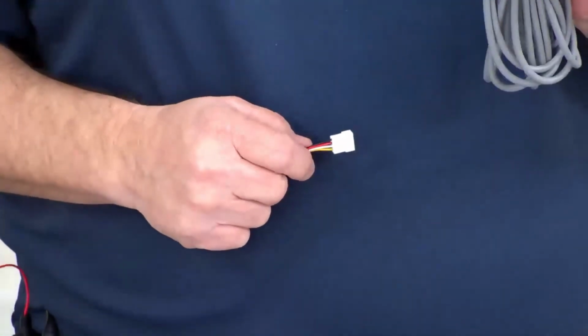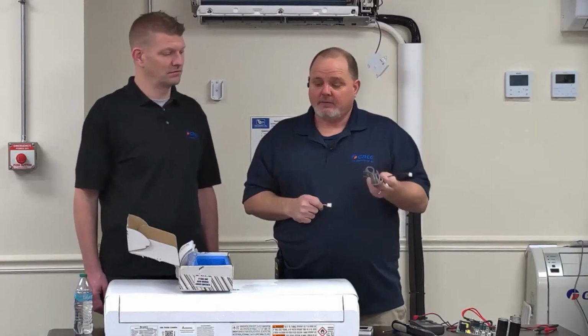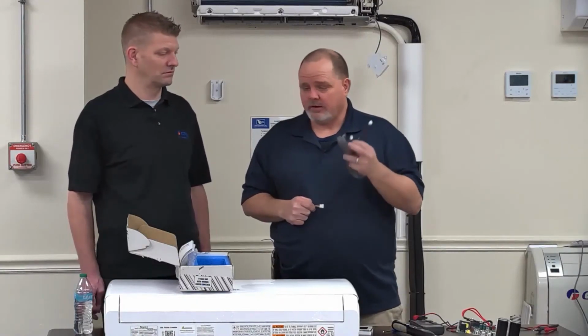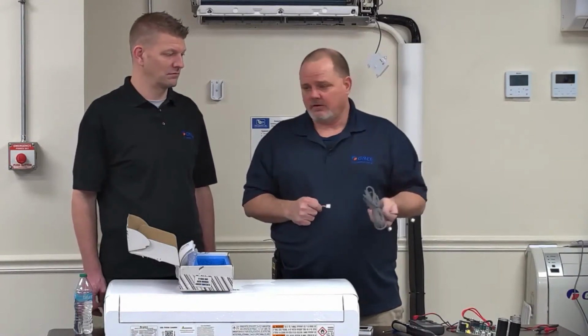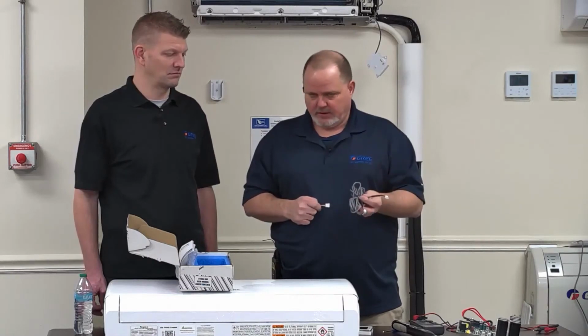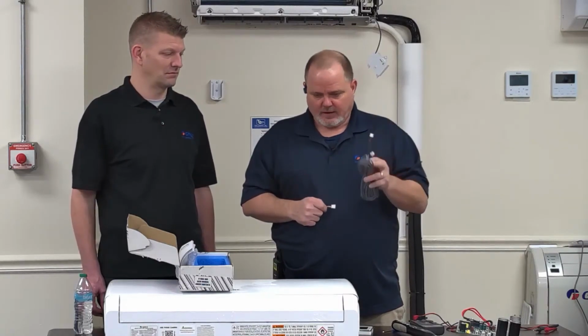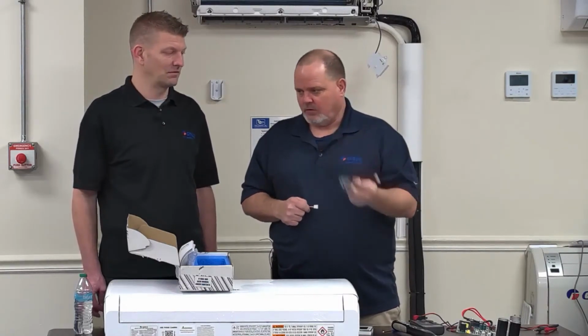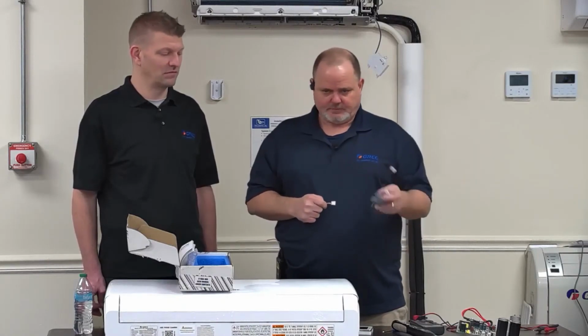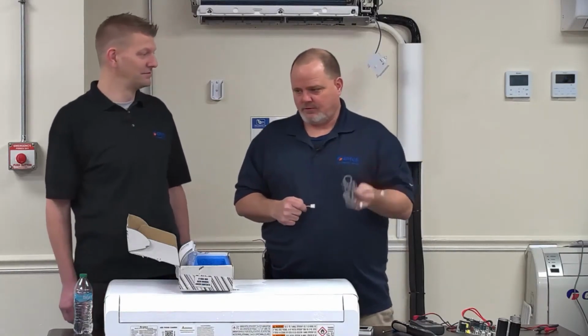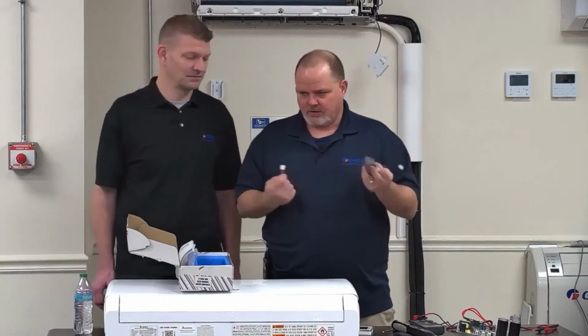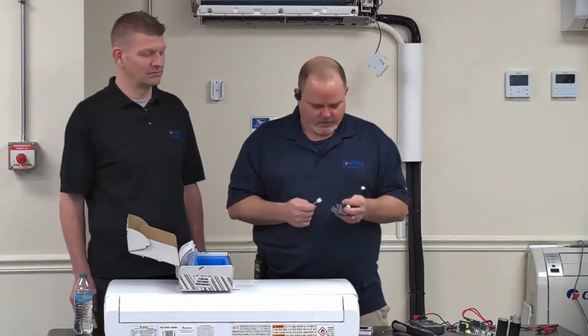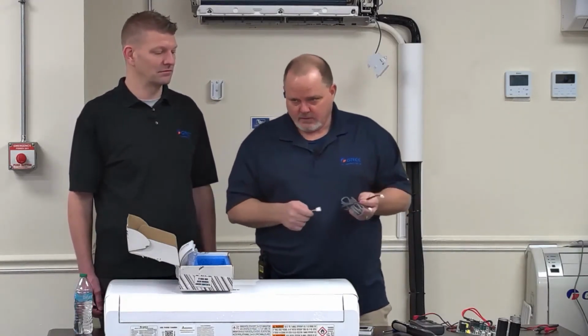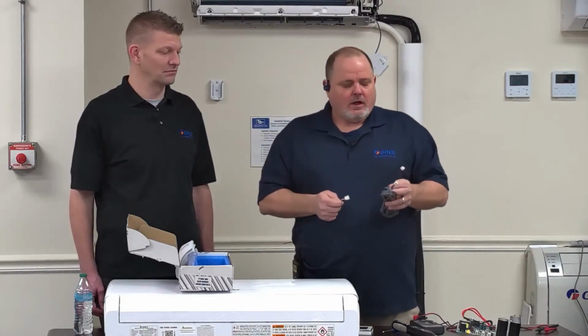That's on the indoor head, right? On the indoor unit. Sometimes there's more than one 4-pin plug. Don't worry about it. You don't need to know the specific number of which one you plug into. The one thing I can tell you is if you plug into the wrong port, it won't hurt the tool, it won't hurt the machine. It's just not going to give you the readings. Just look at the 4-pin plugs, plug it into one. If it works, you got the right one. If it doesn't, you got the wrong one. Trust me when I tell you, it won't hurt the tool.